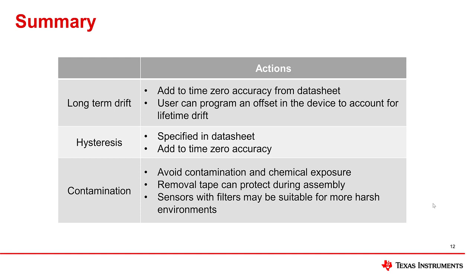Kapton tape can be used to prevent contamination of an open cavity sensor and should be placed over the sensor opening during the assembly process. This tape will need to be removed before operation. A sensor that has a permanent filter installed can be a good option for applications that require more robustness during device operation.